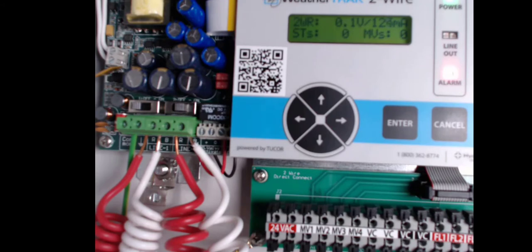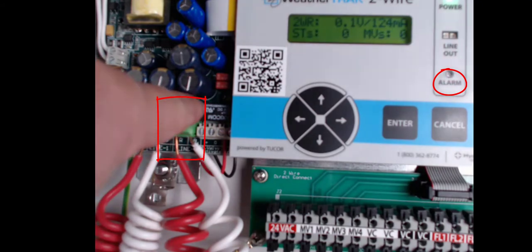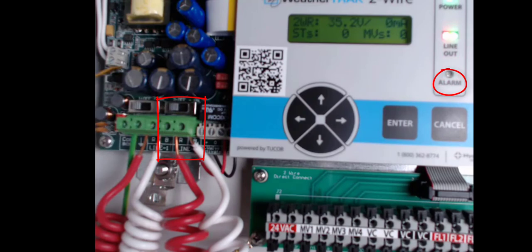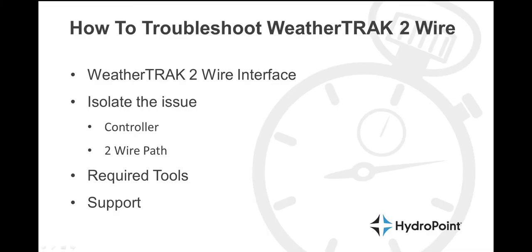Here it is in real time. You see the alert present on the 2-Wire interface — the '2-Wire shorted' message is displayed. I turn off the 2-Wire path that has the known issue on it. It takes the controller a second to reset, but it will go through the process, reset the alert, and go back to its idle state: 35 volts, 0 milliamps. And once we have isolated the controller, we know that the issue is on the 2-Wire path.